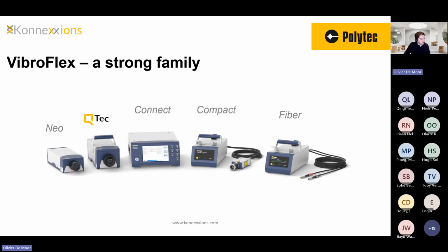The VibroFlex platform consists of the Connect controller and one of the different sensor heads. The Neo is our standard helium-neon sensor head with autofocus functionality. The compact sensor head is also a helium-neon sensor, but now it's possible to integrate a camera in the compact small head, so you can very accurately target on your object. And it's even possible to attach a microscope objective to measure on tiny objects.